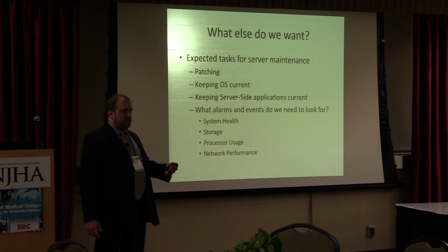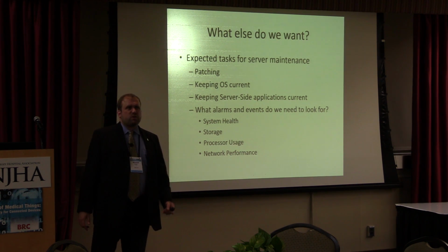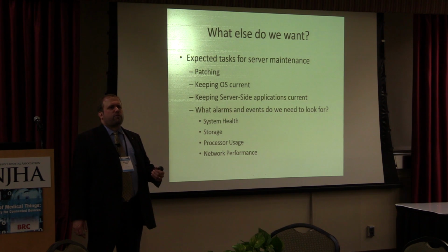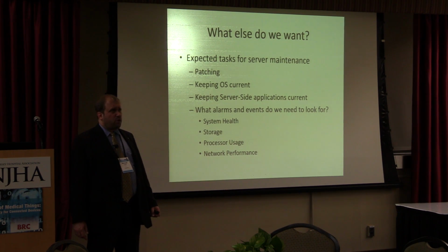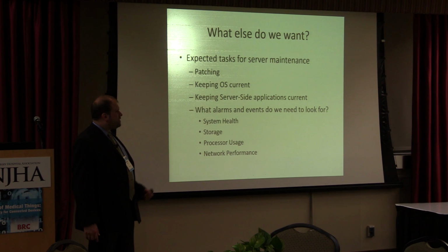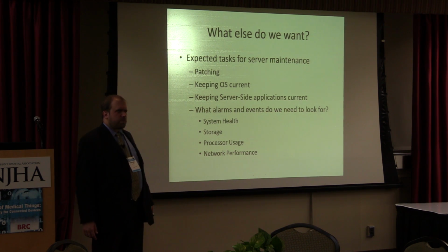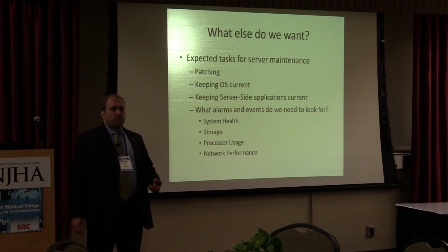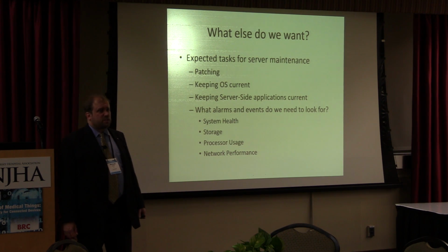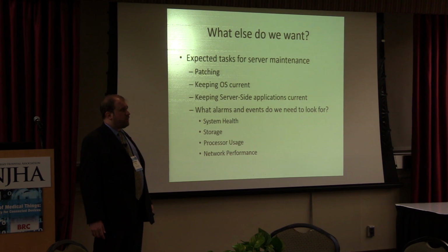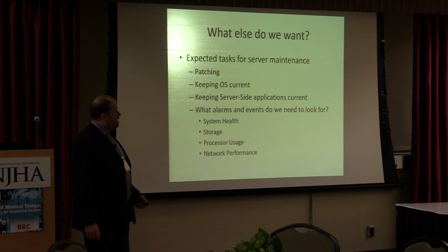So in other words, are there system health alarms? Are there storage alarms? Am I going to get a phone call from you going, oh, we didn't tell you this, but your virtual machine needs another 2 terabytes of storage. I got that phone call last year. What happens with processor usage? How do we monitor that? How do we monitor network performance? What do we look for? Give us the data we need to actually successfully implement your device or your virtual machine in our environment.